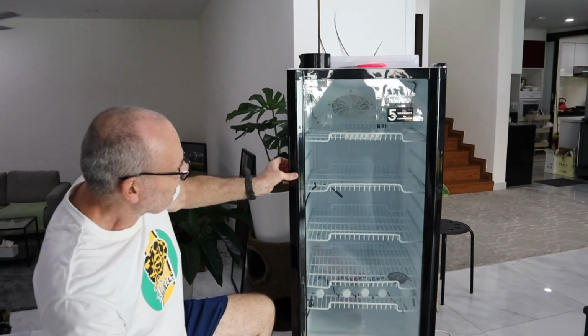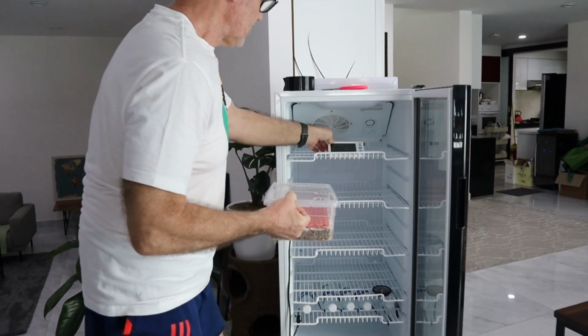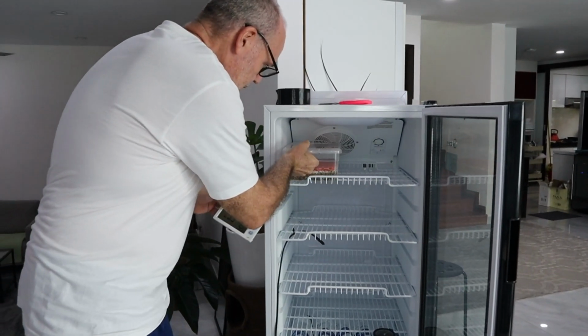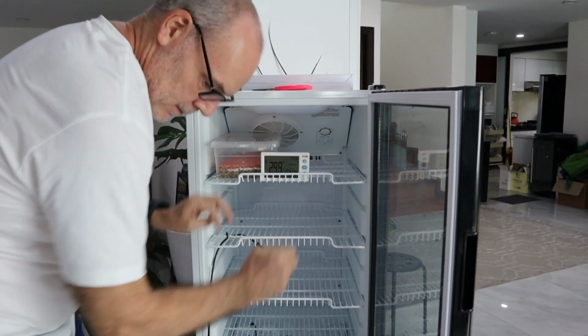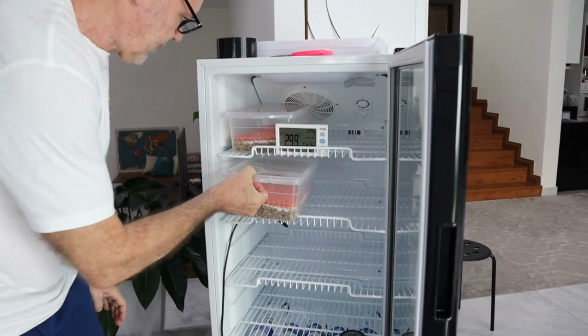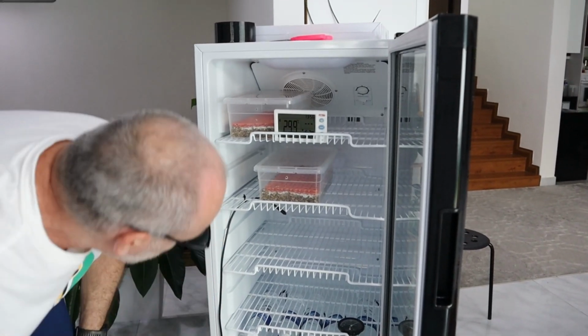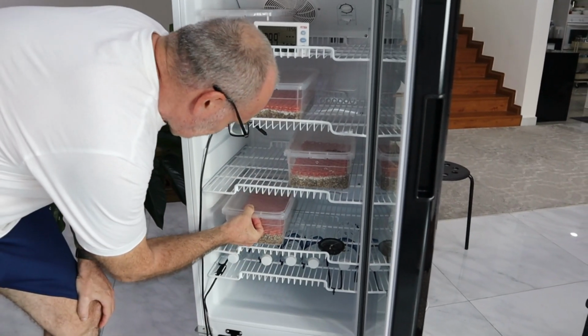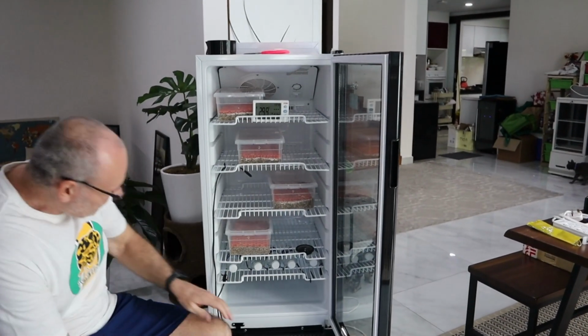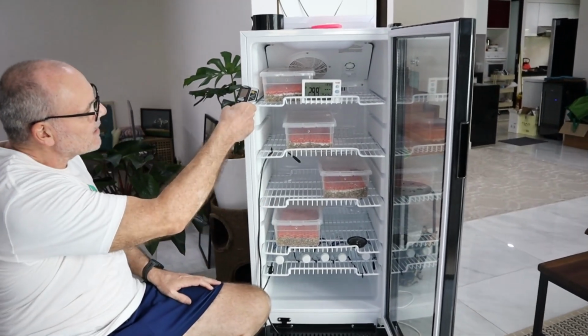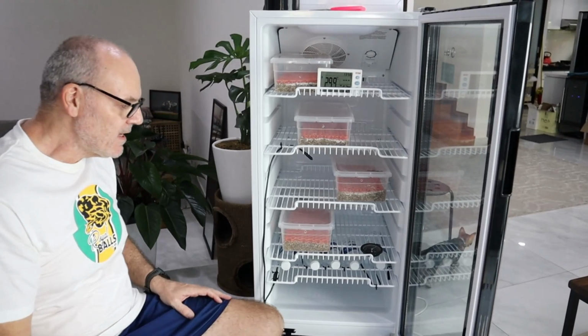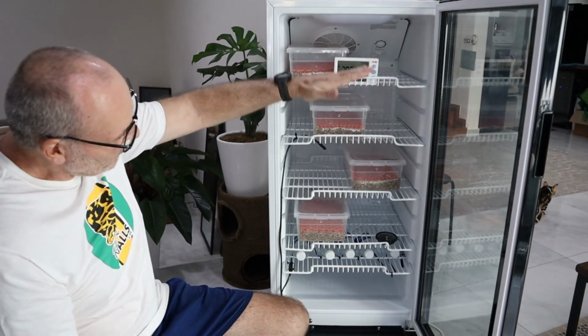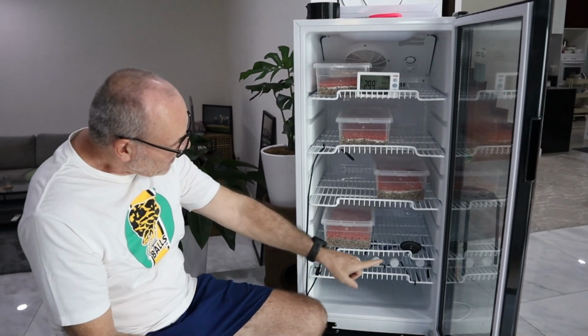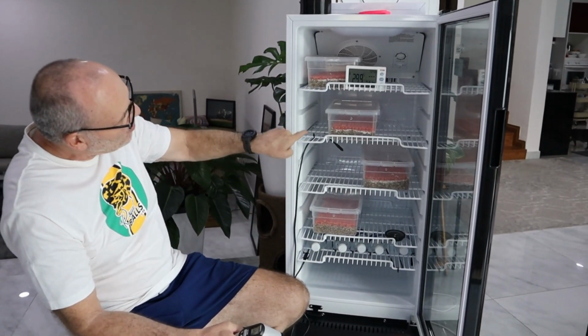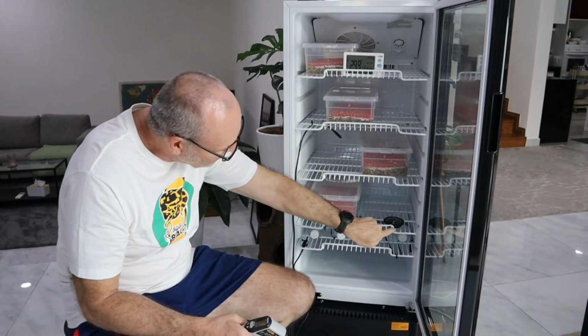Okay, so what I'm going to do with these trials is also I'm going to put an egg box on each of the 4 shelves. One on the top shelf, one on the middle shelf, and one on the bottom, so that when the incubator is stable, I can get a temperature reading on the bottom, I can get a temperature reading on the top, and find out whether there's a heat gradient. Now remember that it's convection that's causing that heat gradient. There is actually air moving, warm air moving up to the top and cool air moving down to the bottom.